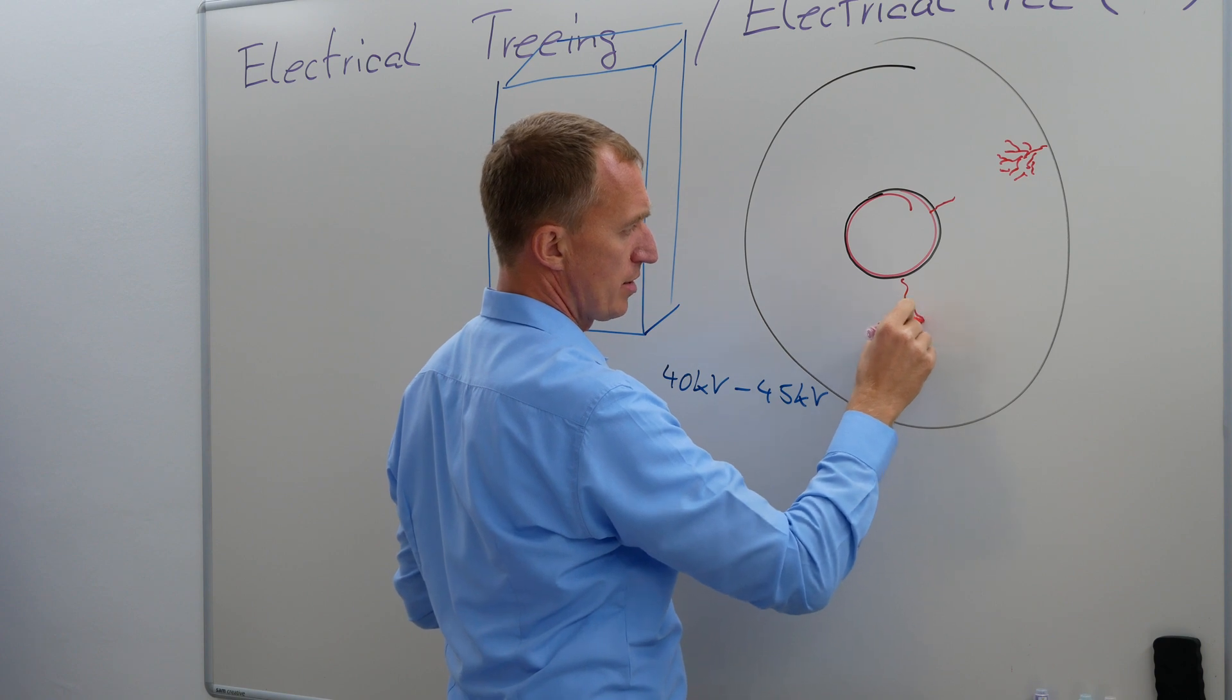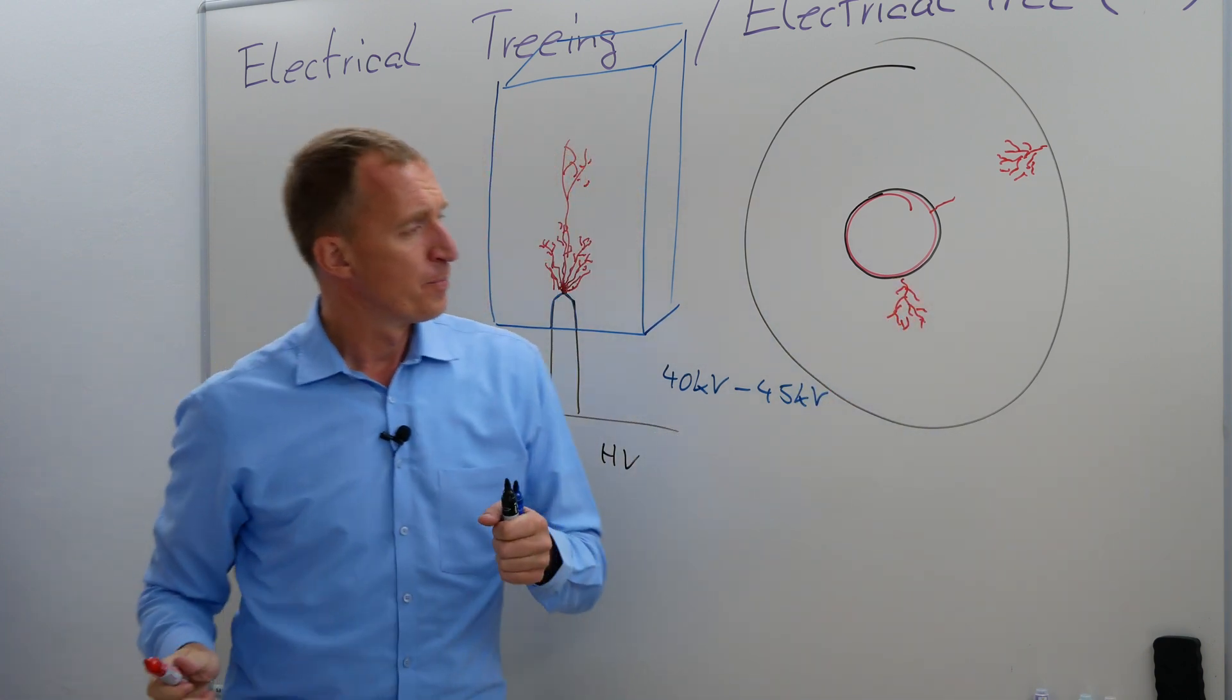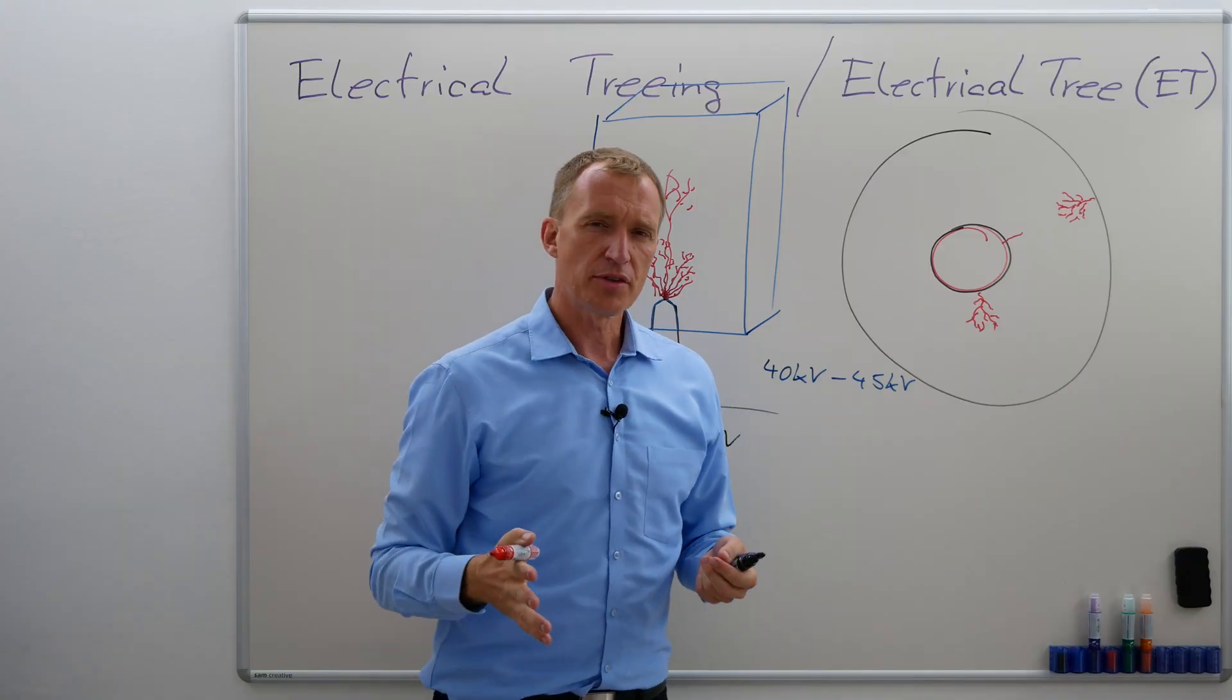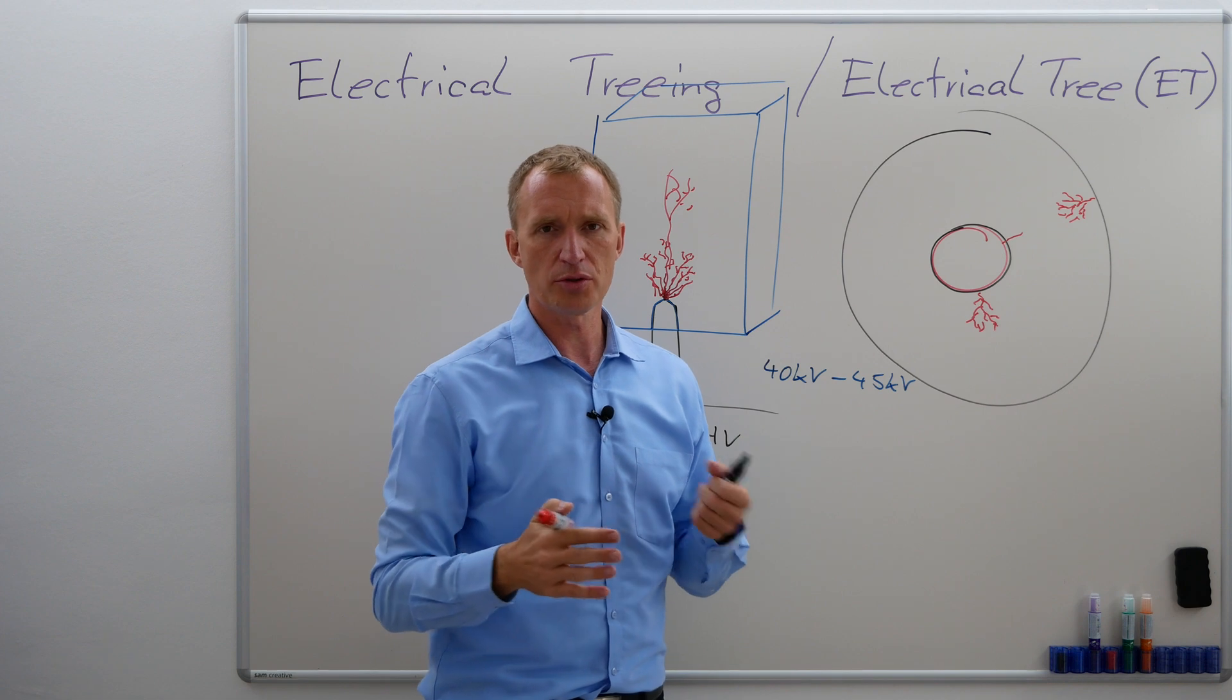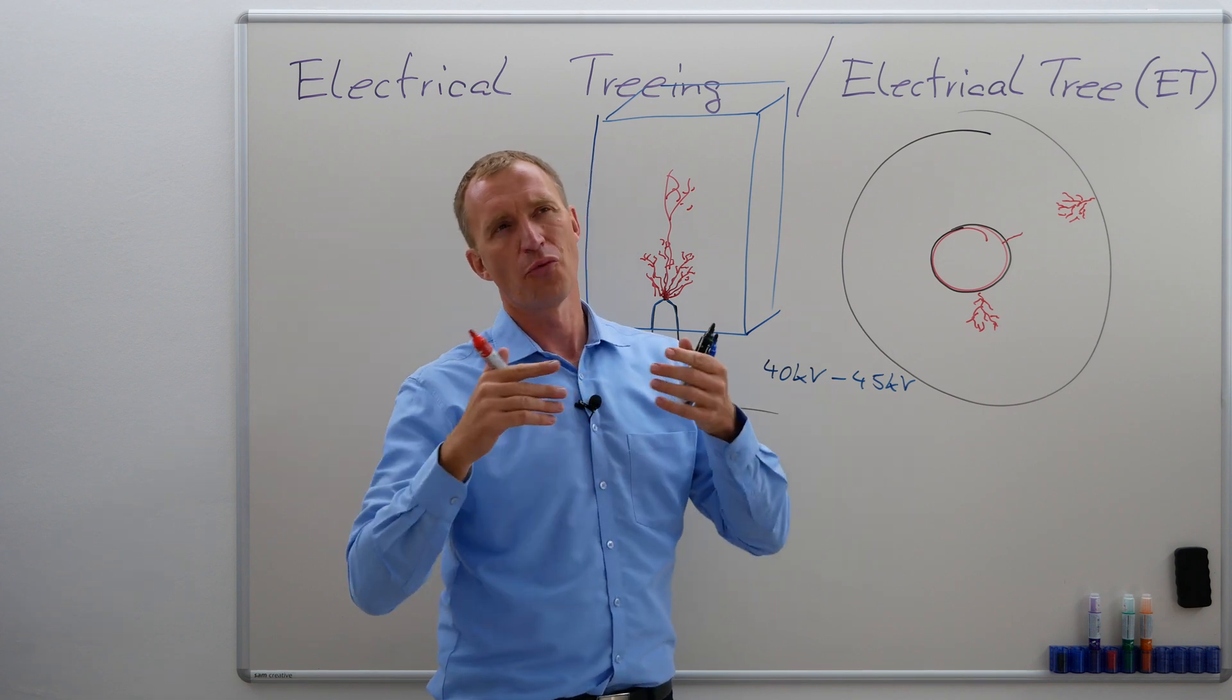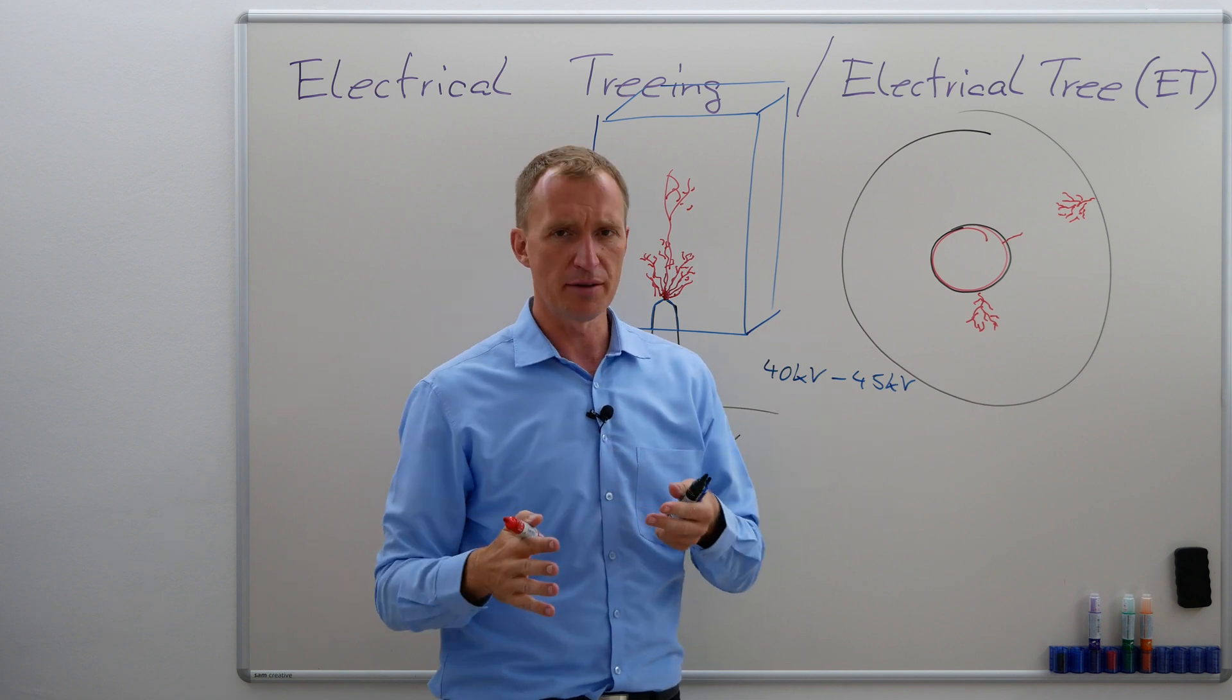Or it grows from the inside to the outside, more and more branches. We also have something which is called water trees. And for a long time people thought that water trees fail cables. Water trees, from my perspective, and there's a paper about it, they don't fail cables by themselves.